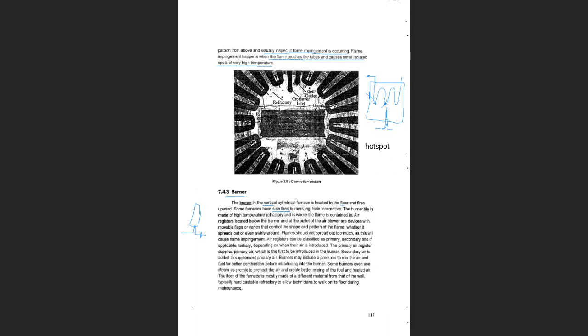And this control valve is known as what is called an air register. هذا الـ air register, شباب, this is very important. And if you work in a furnace, most likely you will have to turn them up and down. You will have to notch it up a little bit or notch it down. تفتح الـ air register شوي أو تقفل.